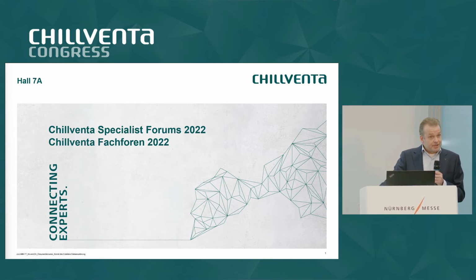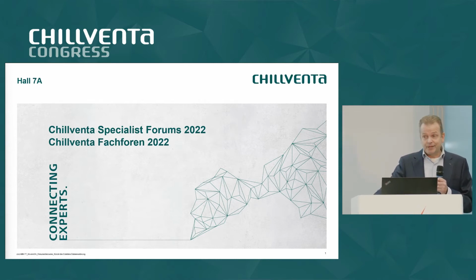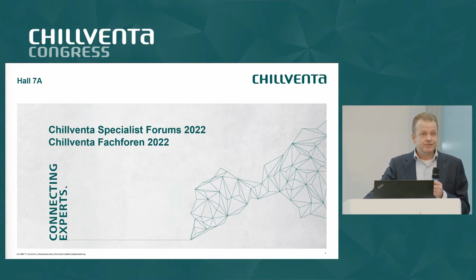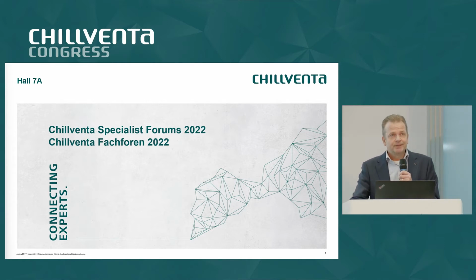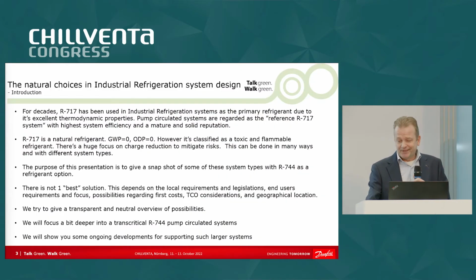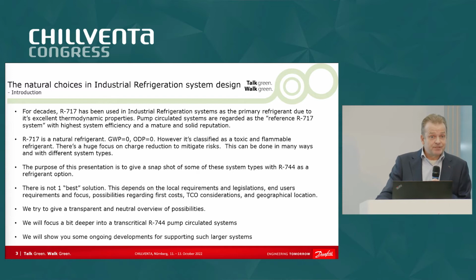The refrigerant itself is ammonia, most of the cases. Ammonia has a very high efficiency. The thermodynamic properties are super good. It's a natural refrigerant. The global warming potential is 0. Ozone depletion potential is 0. So you would say, what is wrong with the refrigerant? Well, nothing wrong, but it is classified as toxic and flammable.